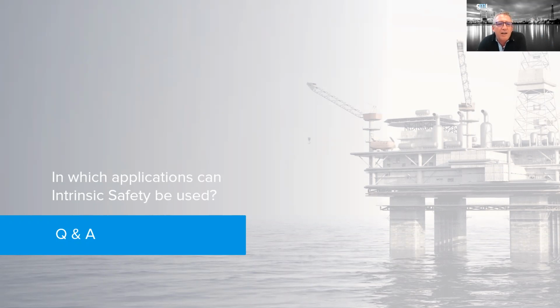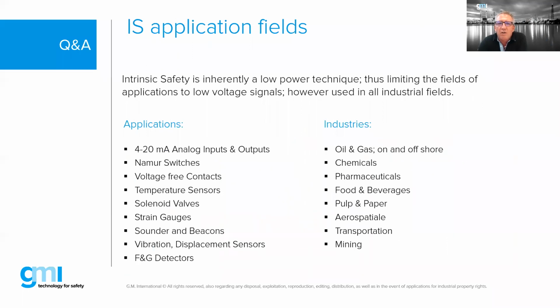In which applications can intrinsic safety be used? This is a generic question. A lot of our sensors - measuring temperature, pressure, all different kinds of sensor devices - commonly use intrinsic safety. Fire and gas systems too, and it could be oil and gas, chemical, pharmaceuticals, all different kinds of facilities. It could involve hazardous gas or be used in dust atmospheres. Intrinsic safety has been around a long, long time and is widely used - it's one of the most popular protection concepts out there. But it's only one of many different protection concepts, and certain things you just cannot make intrinsically safe. For many of your sensors, your 4 to 20 milliamp type devices, it's absolutely right up the alley to make them intrinsically safe.